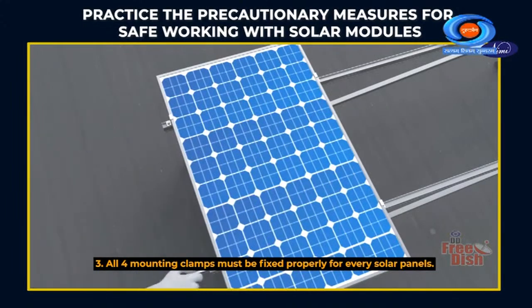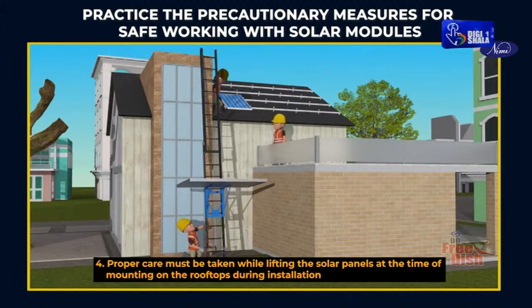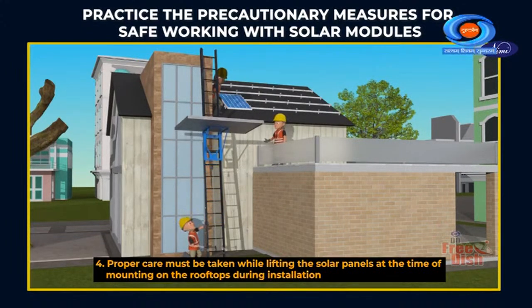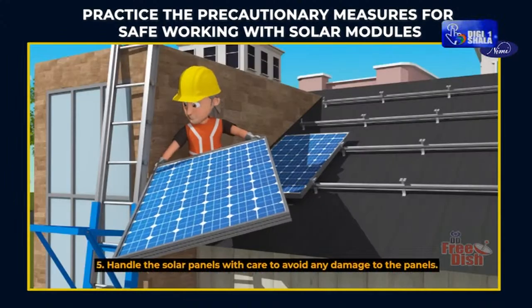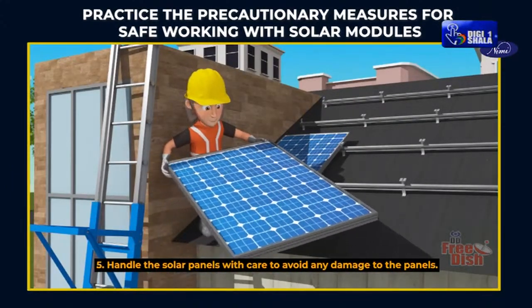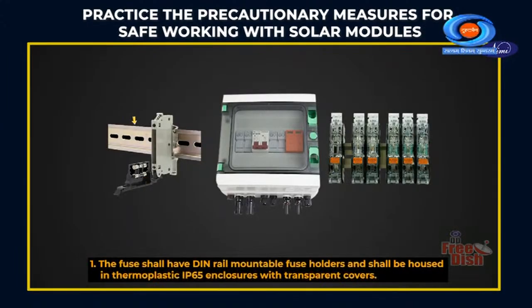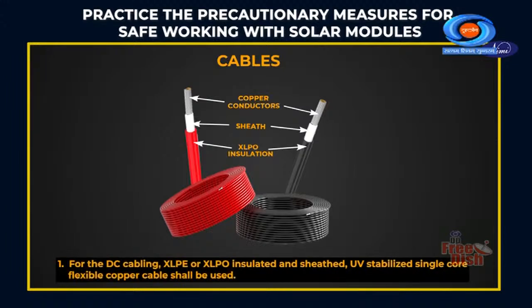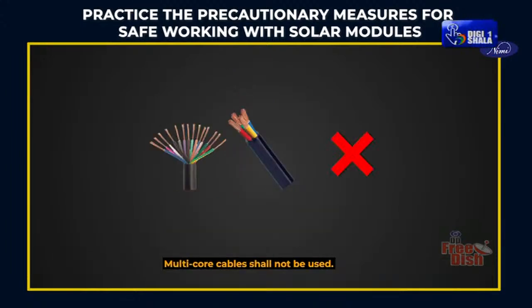All 4 mounting clamps must be fixed properly for every solar panel. Proper care must be taken while lifting the solar panels at the time of mounting on the rooftops during installation. Handle the solar panels with care to avoid any damage to the panels. Fuse: the fuse shall have DIN rail mountable fuse holders and shall be housed in thermoplastic IP65 enclosures with transparent covers. Cables: for the DC cabling, XLPE or XLPO insulated and sheathed, UV stabilized single core flexible copper cable shall be used. Multi-core cables shall not be used.